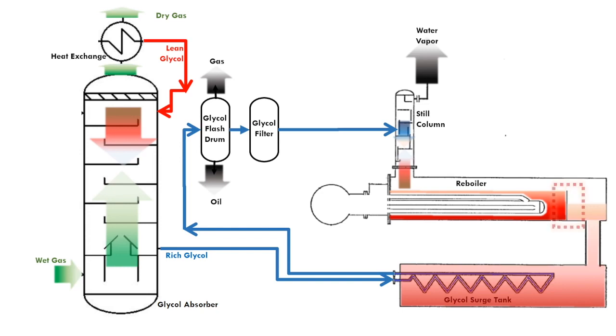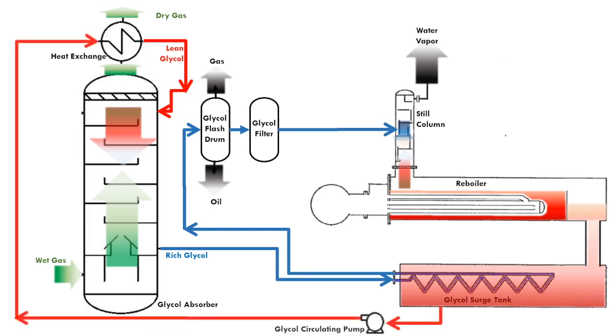The glycol in the reboiler is maintained above the fire tubes of the heater by a weir. The lean glycol overflows down into the glycol surge tank. The lean glycol is circulated back to the glycol absorber using the circulating pump.